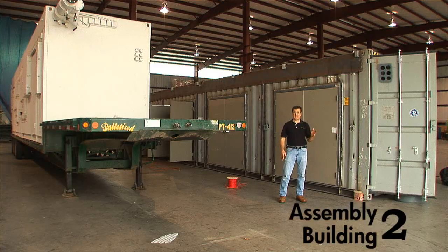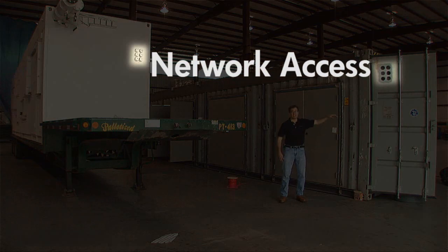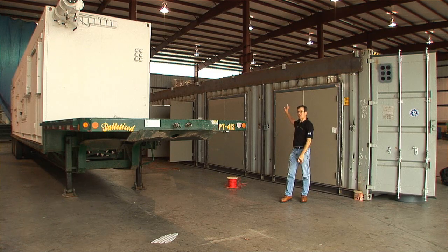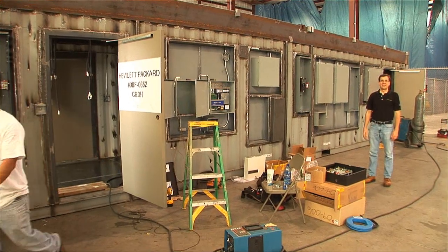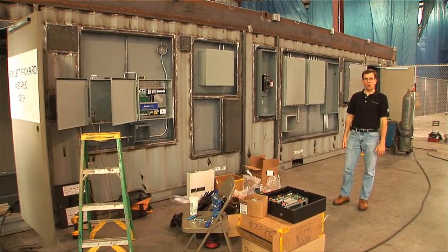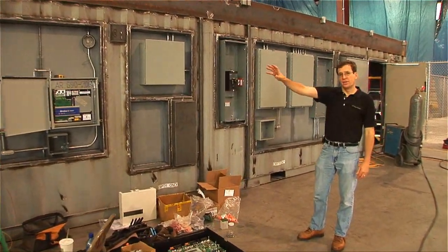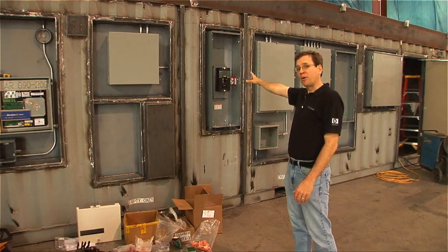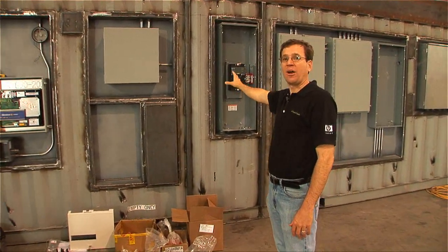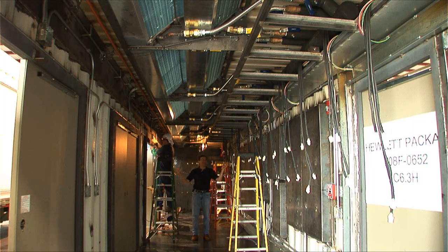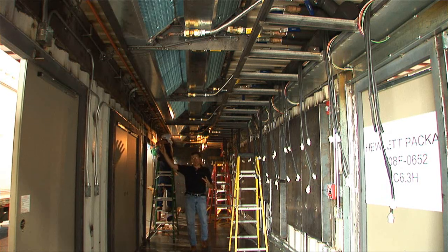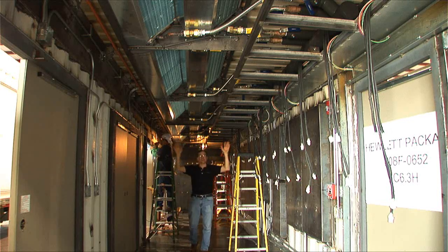Some of the modifications were for network access and all the doors along the hot aisle. There's modifications for cold aisle doors, control, safety, and of course power distribution like you expect in your regular data center. It doesn't look a lot like a data center right now, but you really get to see all the conduit, all the power distribution, and the exposed heat exchangers and attic.